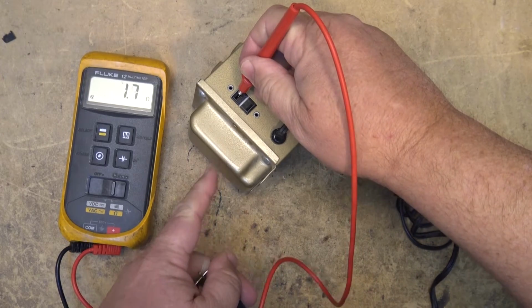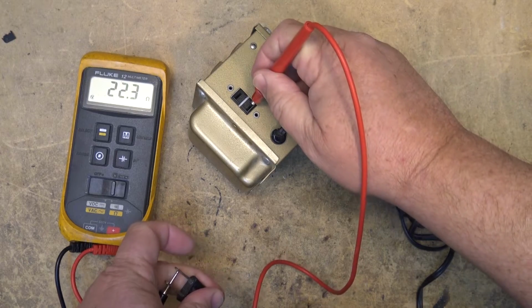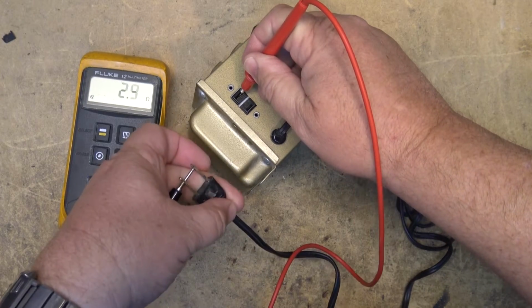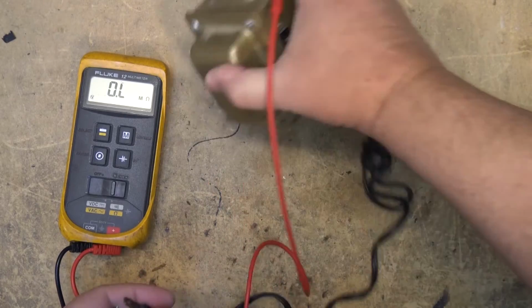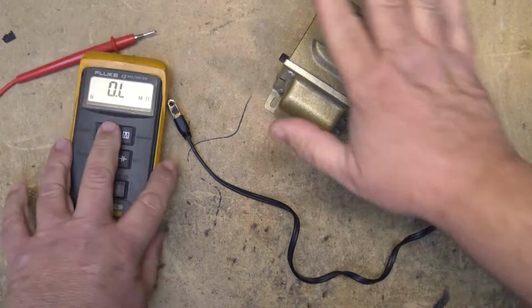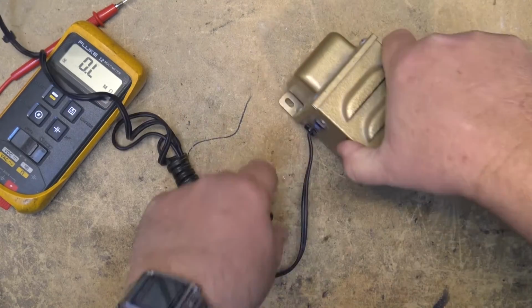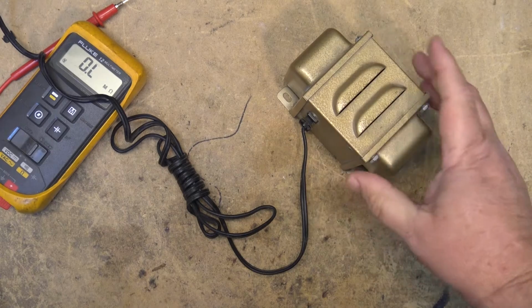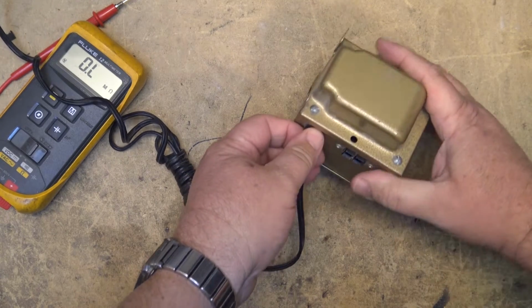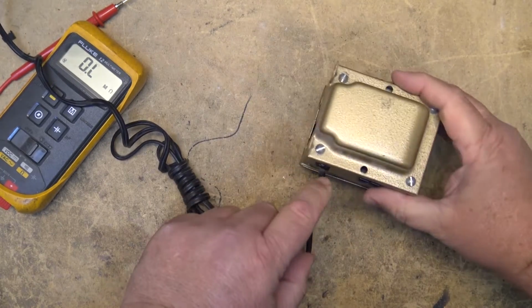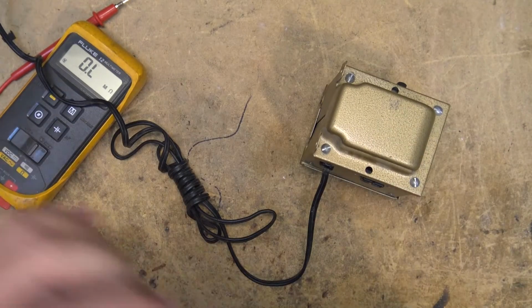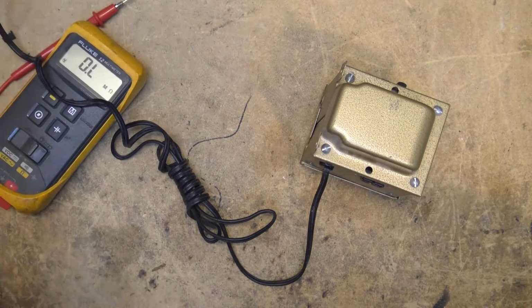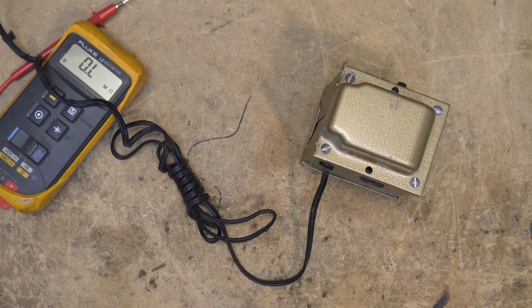And as you can see, we have continuity. So this is not an isolation transformer at all, but we can probably make it one, because I'm sure it probably is isolated internally. It's just that they've attached the neutral to the neutral on the plug. So let's open this thing up and take a look at what's actually inside this unit, because we know it's going to be a transformer with at least 2 taps on it.